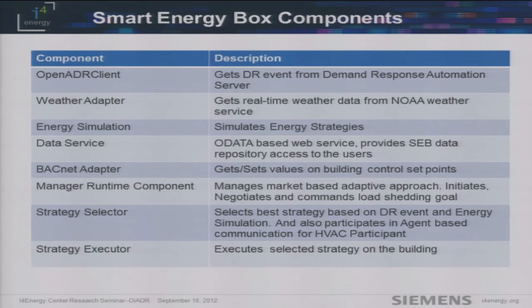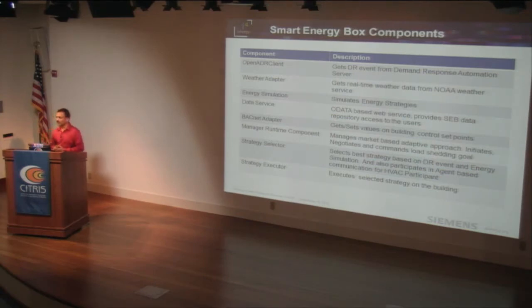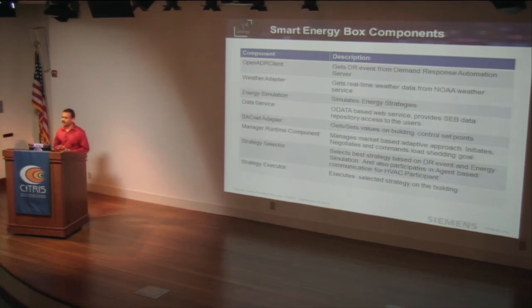These are the components currently available in the Smart Energy Box: OpenADR client which brings in the DR signal, weather adapter, energy simulation, data service for exposing data, BACnet adapter for communicating with the building management system via BACnet over IP, and a runtime manager which is the key component that plans overall load shedding — both central equipment and distributed control — along with the strategy selector which selects the best strategy using energy simulation.